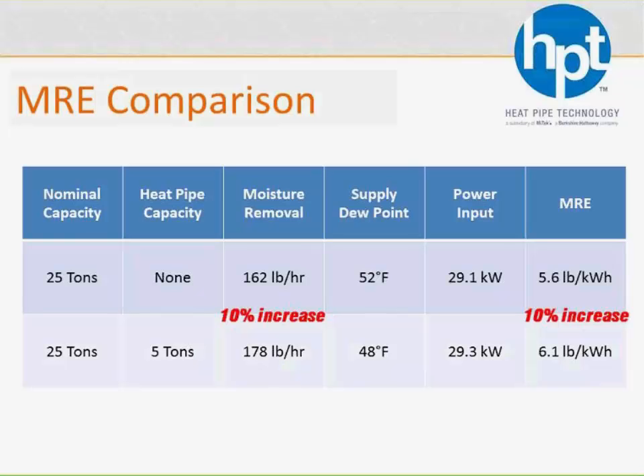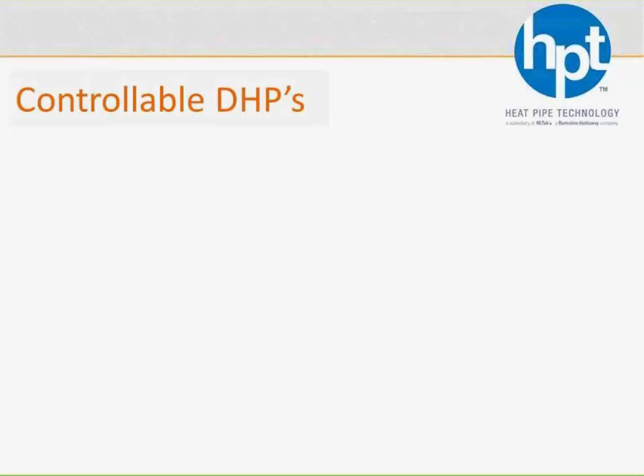So when looking at these wraparound heat pipes, whether you're looking at it from a capacity reduction standpoint, an EER standpoint, an MRE standpoint, or drying it out even further to drop that dew point down, there are not many ways to do that while also getting the free reheat from one device, and that's what the wraparound heat pipe is doing for you. So I want to take this even further. At this point, we've talked about how to optimize the dedicated outside air system with a heat pipe. Now let's talk about how to optimize the heat pipe, which of course is going to optimize your system even further. And of course, I'm talking about making it a controllable wraparound heat pipe.